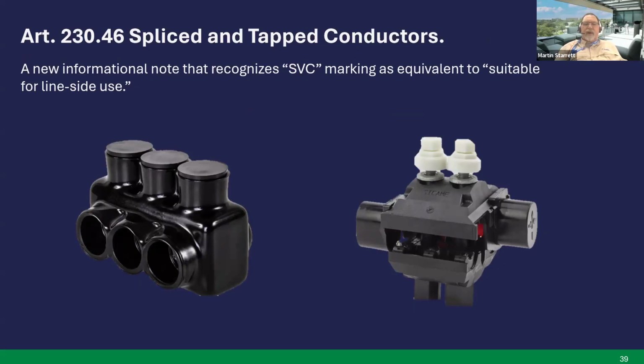Article 230.46, splice and tap conductors. There's a new informational note that recognizes SVC marking as equivalent to suitable for line side use. So if one of these devices doesn't have suitable for line side use, as long as it's got that SVC marking, it will be okay.